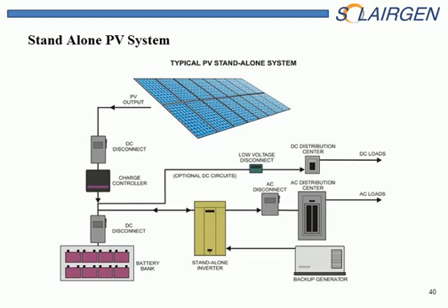Here's the linear flow of a standard standalone PV system. So this would be an off-grid system with no utility anywhere near it. It could also be grid connected, but actually a standalone, just using the grid as a backup, as a generator. So instead of the generator, it'd have a utility connection. This happens occasionally. It's not predominant. What you're seeing is a charge controller that takes and manages the PV energy into the battery bank. These battery banks are probably located in the basement or the garage, and the battery-based inverter would be located at the same location. If there's a generator, it's located, of course, outside.